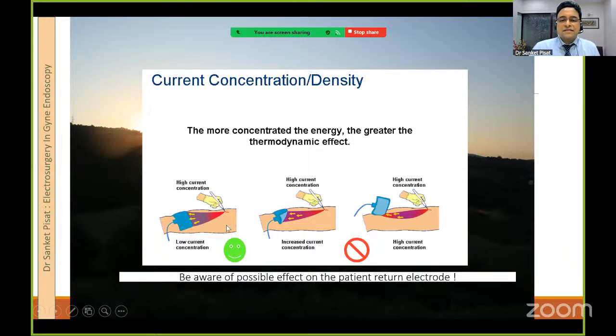So, why does this happen? The answer is in the area of contact. Imagine that a bulk of electrons is entering at this point at a high current concentration. You are forcing a large number of electrons to enter the tissue through a very narrow surface area, and this is going to cause a coagulation or a cutting effect. However, when the same electrons leave the body, they get spread out over a wider surface area, and therefore this will not cause a burn.